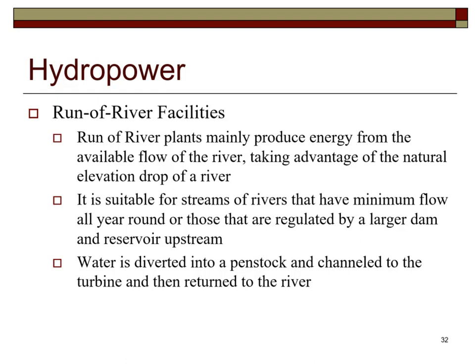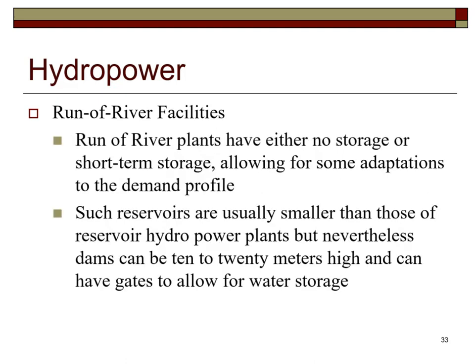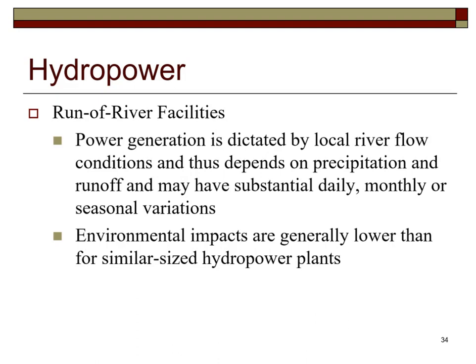Run-of-river plants mainly produce energy from the available flow of water, taking advantage of the natural elevation drop of a river. Water is diverted into a penstock and channeled to the turbine, then returned to the river. These plants have either no storage or short-term storage. Dams can be 10 to 20 meters high, and power generation depends on precipitation and runoff, with potential daily, monthly, or seasonal variations.